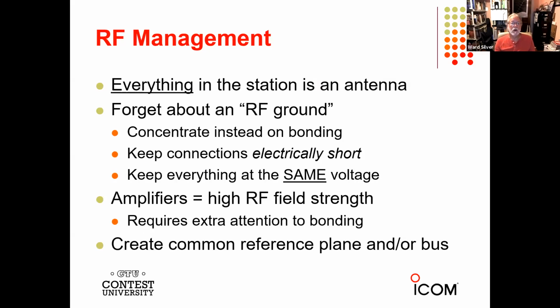So forget about an RF ground. It's just not going to happen. What you can do is concentrate on bonding. Keep all of your connections electrically short, and that'll keep everything at the same voltage. You want it to go up and down together at AC. You want it to go up and down together when a lightning transient hits, and you want to keep it at the same voltage going up and down together at RF as well.